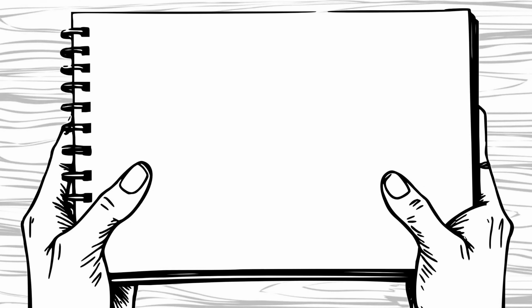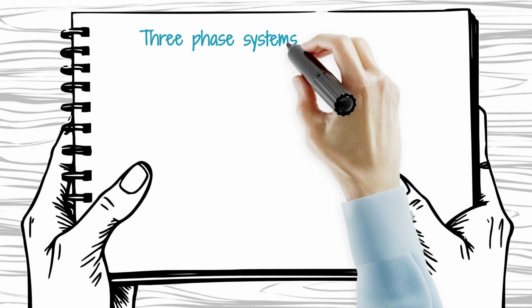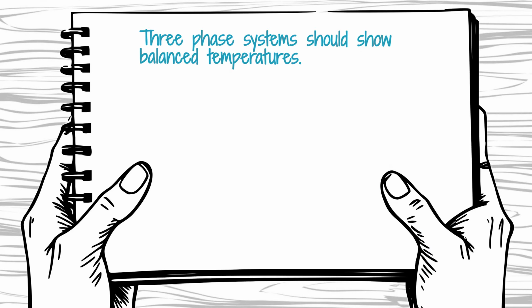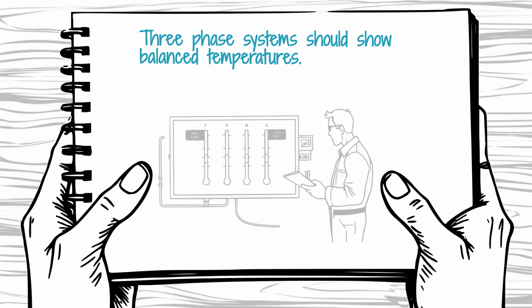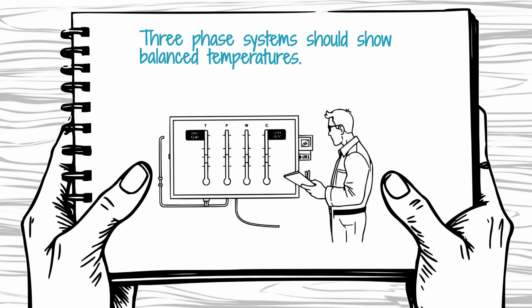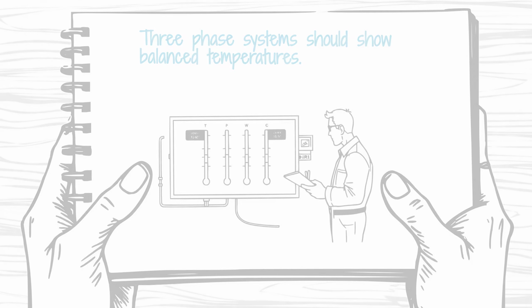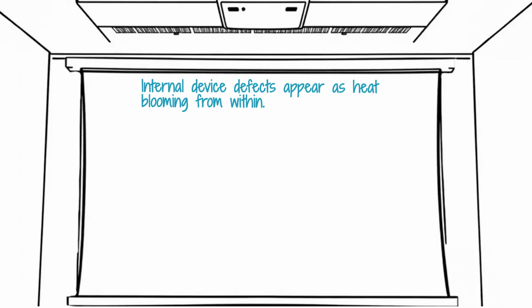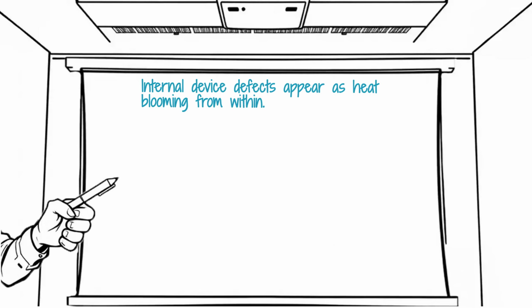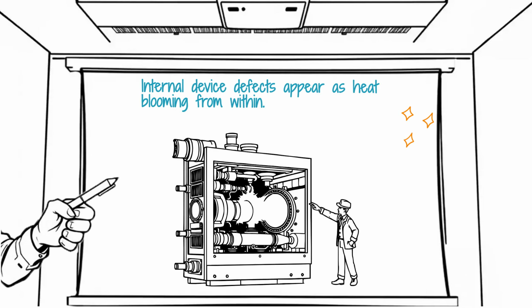In a three-phase system like those found on most ships, a healthy circuit should show balanced temperatures across all three phases. If one phase appears significantly hotter than the others, it usually indicates a high-resistance connection or an unbalanced load. Another critical fault is an internal defect within a component, such as a failing contactor or a pitted breaker contact. These often manifest as heat blooming from within the device rather than at the external terminal points.